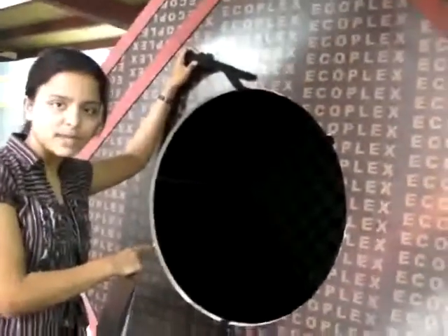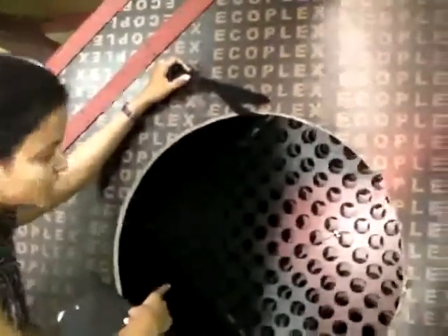The calibration chamber has 4 pressure tapping, which is located as per BS 848, 2 pressure tapping on this side and 2 pressure tapping on the other side. We have also constructed resistance screen as per BS 848. The resistance screen are 60%, 50% and 45% of free area successive in the direction of flow. If you notice carefully, there are 3 thermocouples to measure the temperature inside the chamber. This is about the chamber construction.